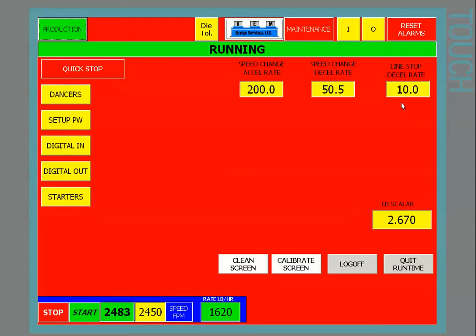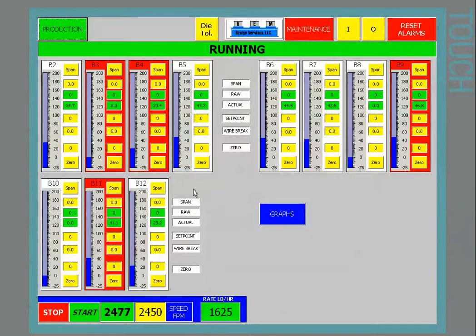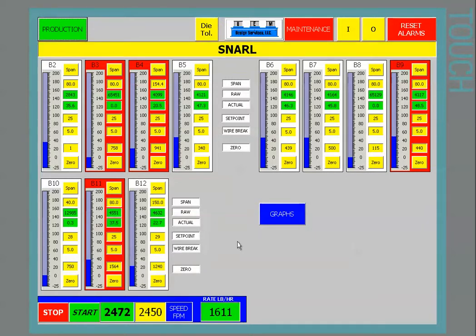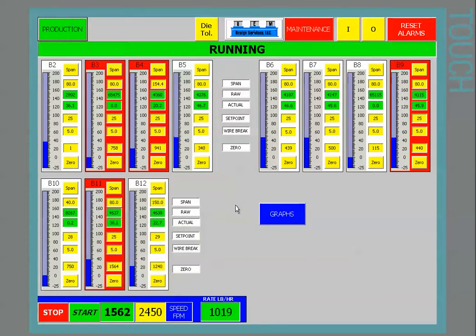The e-stop rate is set for 10 seconds. That's a quick stop. We also have a quick stop button on the screen, which provides the equivalent of an e-stop for the system. Down here we have a pound scaler, and that just sets the scaler for the pounds per hour display. We have a dancer page, and you can see the red ones means that particular block is disabled at that time, but it gives you the position and percent and all the calibration data necessary to run the unit.